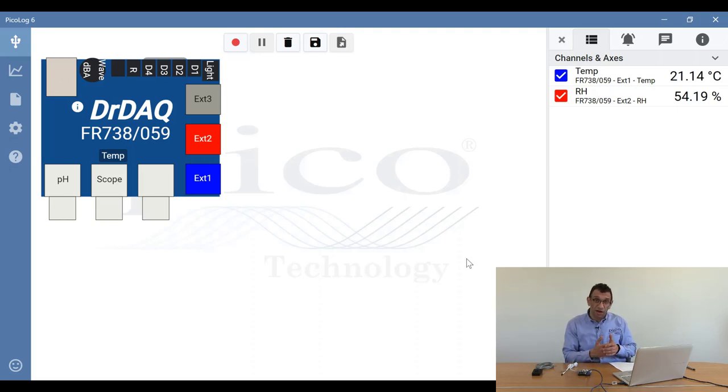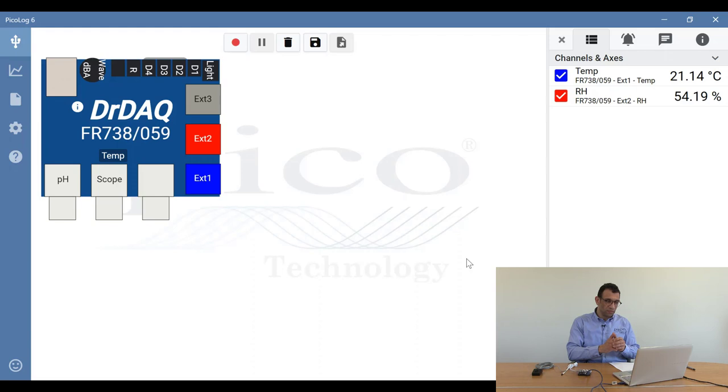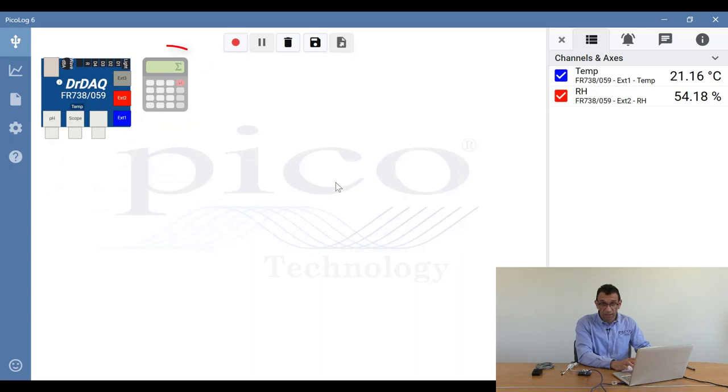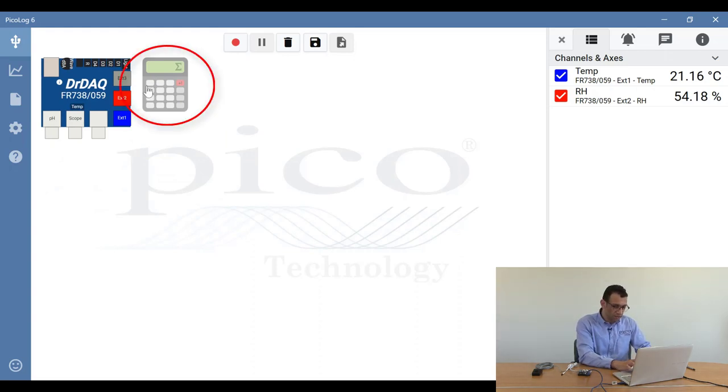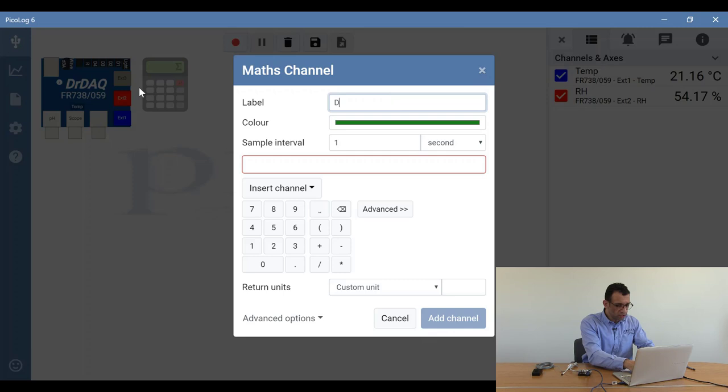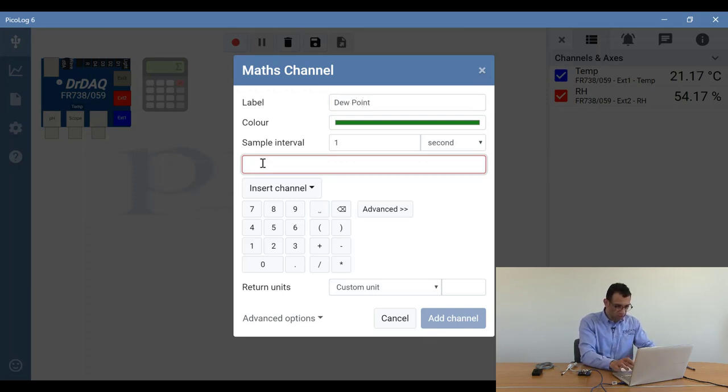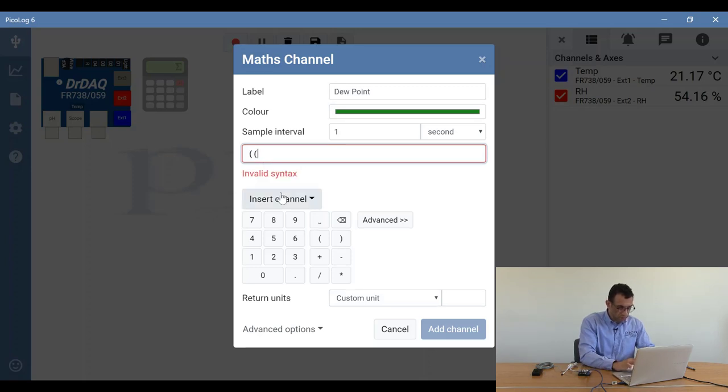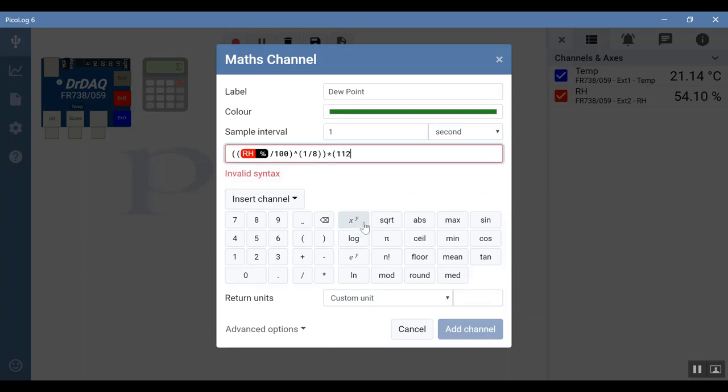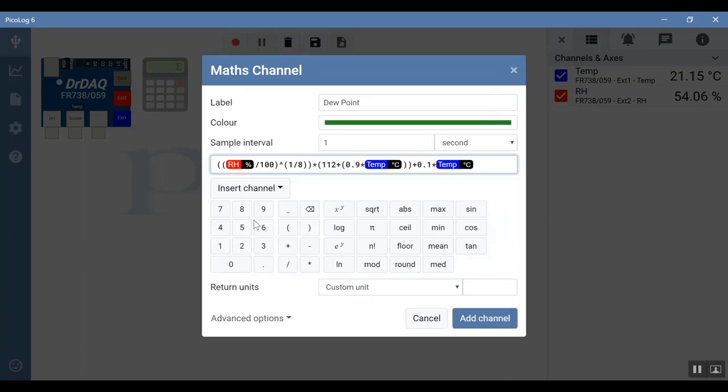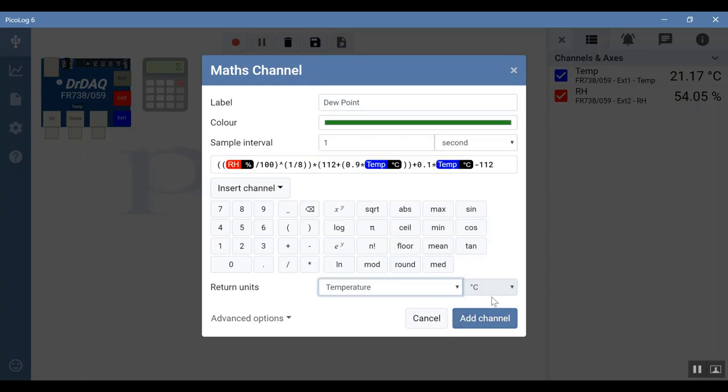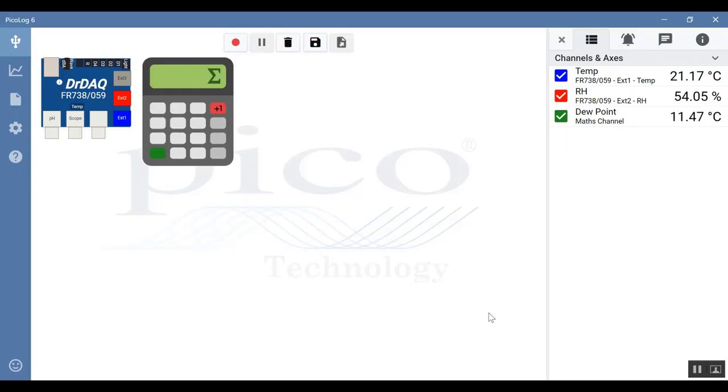We can now add our third channel, which is the dew point channel. If I click on the screen to minimize the image of the DrDAQ, you can see the calculator there, which is where we input our maths channels. I'll click on the calculator to enable maths channels. We'll call this dew point and input the formula for dew point. I'll change the units to be temperature and make sure it's on Celsius because this formula only works for Celsius. Click on add channel, and now we've got a third channel giving us the dew point.